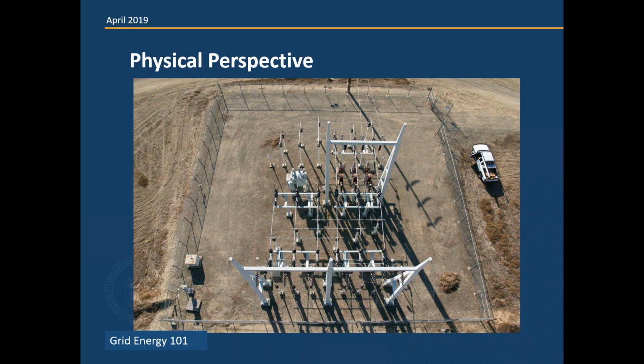So here's a physical perspective. This is a picture of a little pumping plant near Fresno, California. The line crew was in a bucket and they snapped this photo for me. So for the field worker out there who's working on equipment, this is what it looks like to them. The line comes in at the top of the screen. It goes left and through a circuit breaker, and then splits on a little jack bus. Then it feeds down to a pumping plant where there's a couple of transformers. Next slide, please.